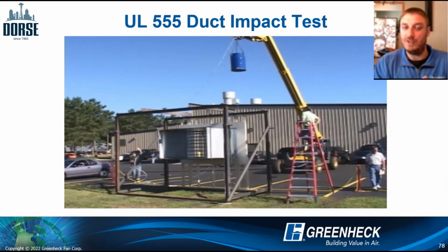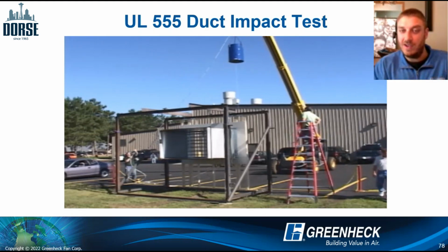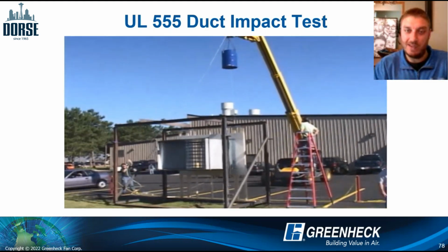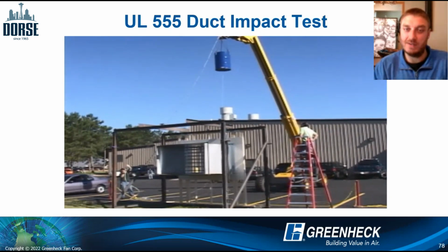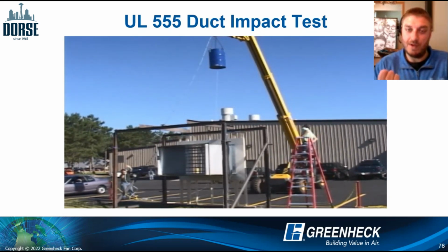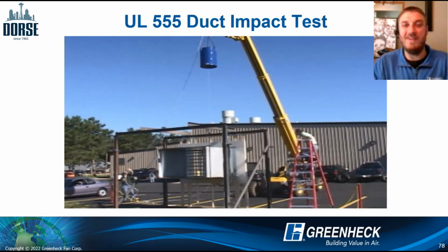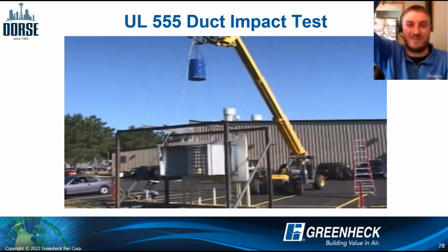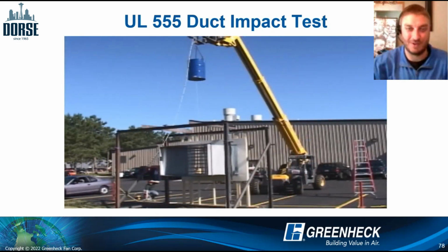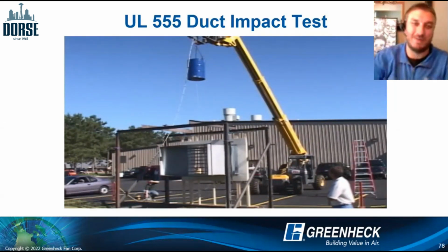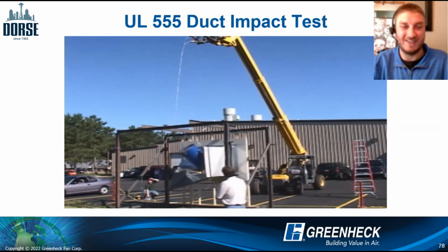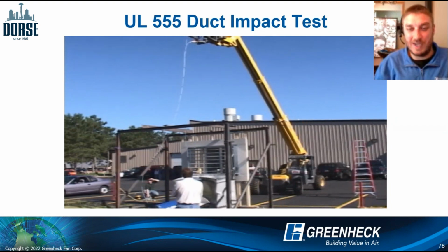So we have to do this super awesome test where we take a 55-gallon drum, fill it with 400 pounds of sand, and raise it 10 feet above the damper. It's so funny because you're measuring with a string and a calibrated tape measure 10 feet, and then you're just taping it to the bottom of this barrel and dropping it on the duct and just kind of watching the carnage.